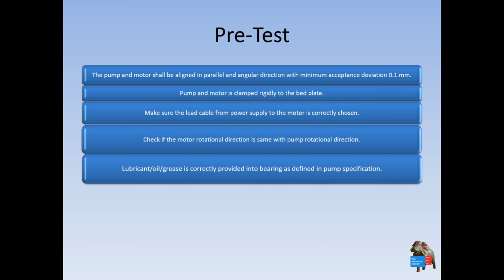And then you have to check the lubrication of the pump, because sometimes pumps have a lubrication housing, so you don't want to test the pump with no lubrication and generate excessive heat, and damage the bearing, etc.